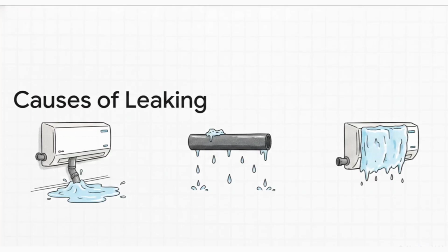So why does this happen? Well, water pooling is very often just a fundamental installation issue. If the drain pipe slope isn't angled downward correctly, water just pools inside the tray instead of flowing outside. And eventually, it overflows right down your wall. Another massive culprit here? Uninsulated copper pipes. When the warm air in your room hits those naked, freezing cold pipes, the moisture in the air turns into water droplets, literally sweating. And finally, choked air filters. These can restrict airflow so severely that the internal cooling coils actually freeze over. Then, when the AC turns off, all that ice melts into a huge, watery mess.